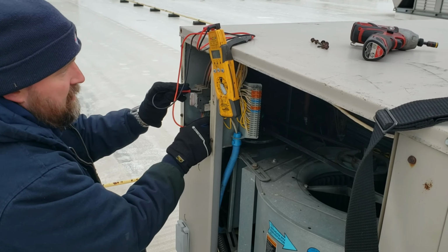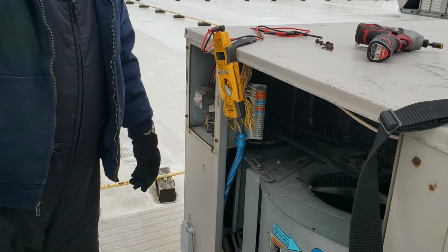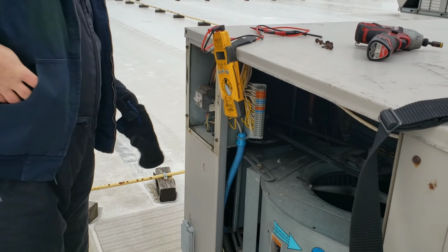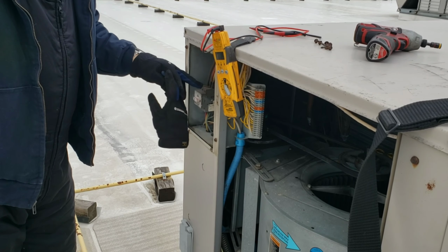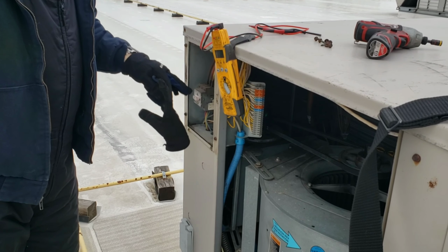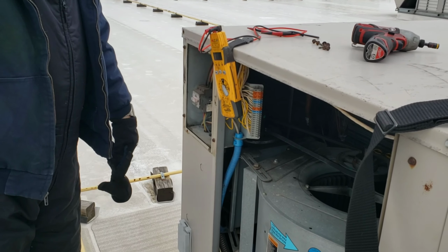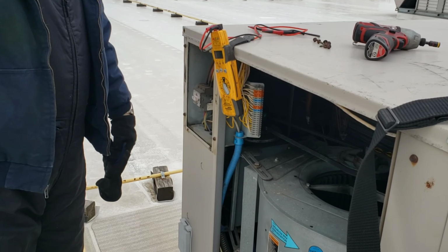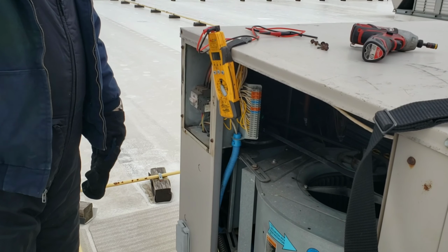So I'm gonna shut it off. We're gonna go downstairs, find the breaker, come back up, and try again. All I did was check from one leg to the other, to ground. When I come back up, I'll go across both terminals. It's 3-phase, 208, 230, so we want to make sure we have voltage there.